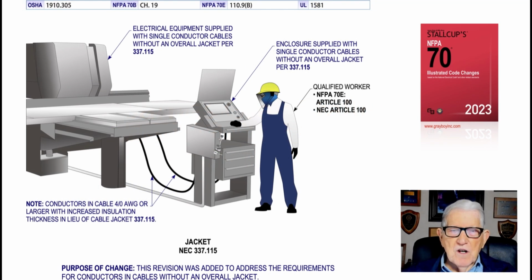Now, this illustration deals with a jacket requirement on a cable in accordance with 337.115. And the purpose of the change is to allow a cable with insulation at a certain thickness, more than normal, to be routed without an overall jacket. And as you can see in the callout at the top left of the illustration, it points out that this is equipment in accordance with 337.115, and the enclosure supplied with a conductor without an overall jacket. And then the note outlines it all. It says conductors in a cable 4/0 AWG or larger with increased insulation thickness in lieu of a cable jacket is permitted in accordance with 337.115. And that's what this illustration is illustrating to the user of the NEC.